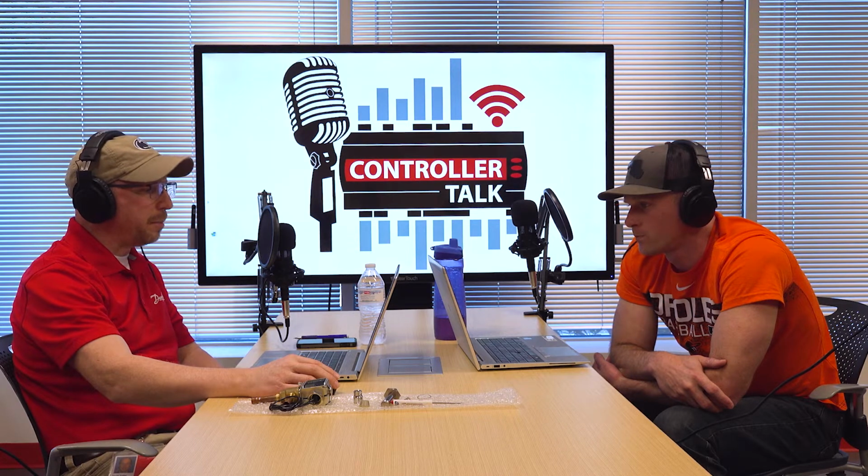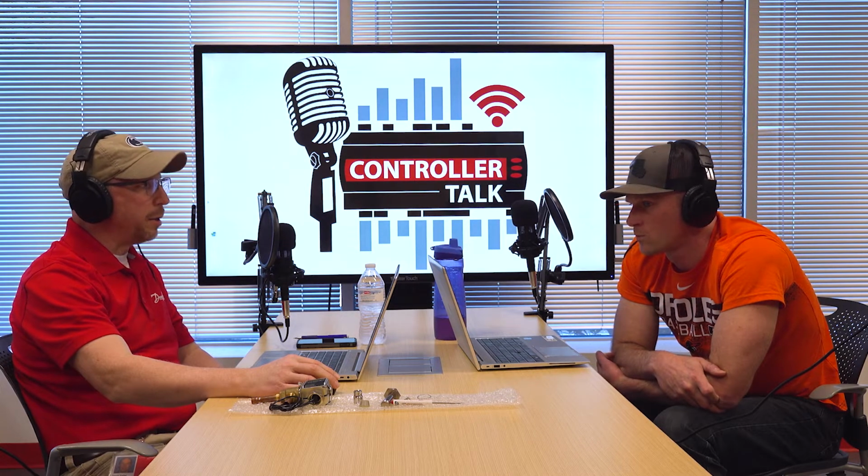One of the things that makes guys scratch their heads when it comes to these valves is how to troubleshoot them and when you have to open it up. Just real quick, one other point on the sizing that these OEMs are doing. There's some overlap in the capacities between the valves, so it's not that there's only one right answer. Sometimes there could be 2 or 3 different sizes of the AKV that could work for the same case. So there's a little bit of flexibility from that standpoint too.